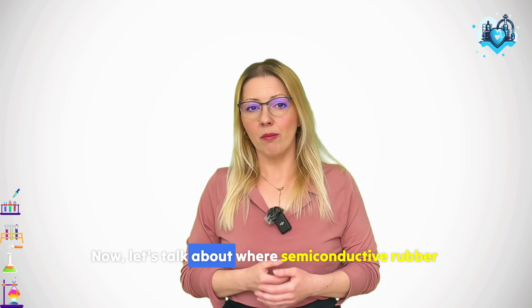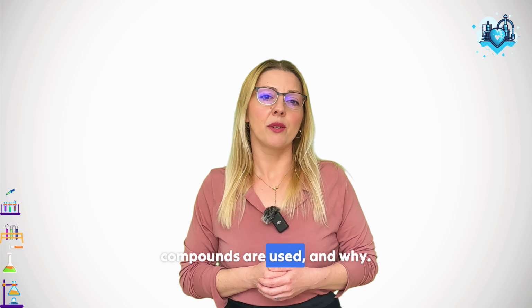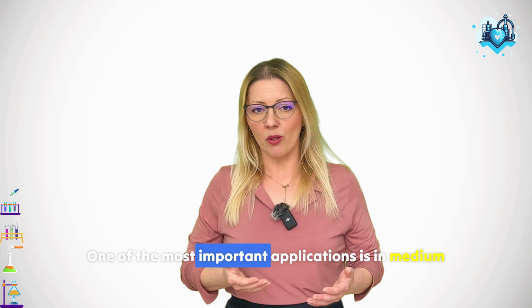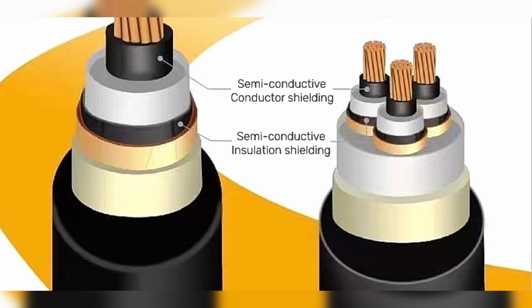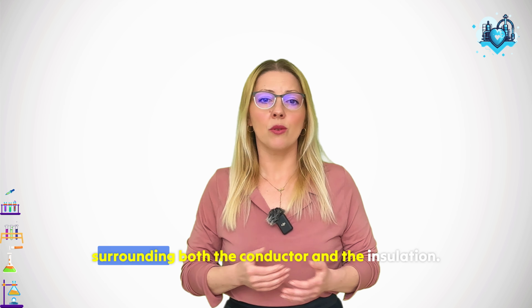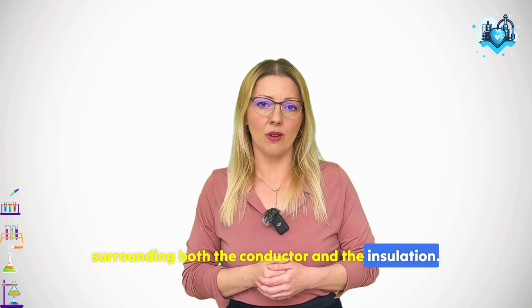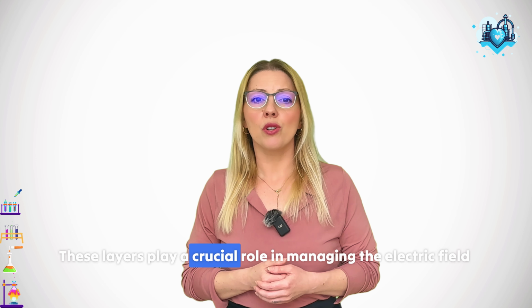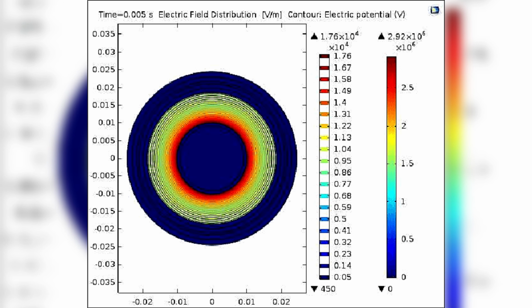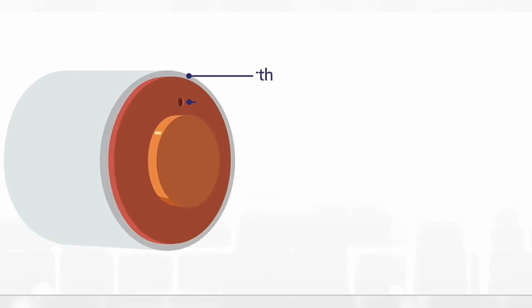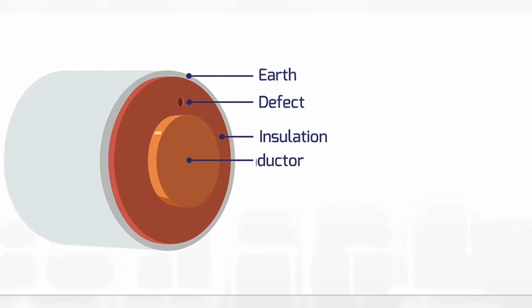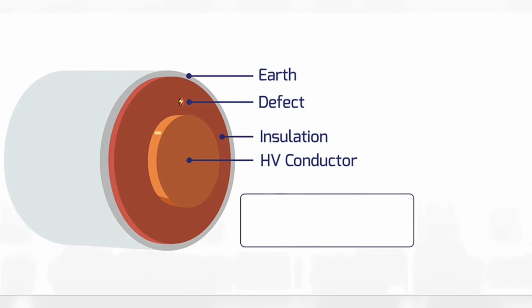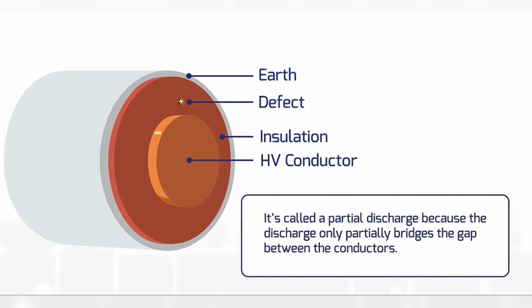Now, let's talk about where semiconductive rubber compounds are used and why. One of the most important applications is in medium and high voltage power cables, where you will find semiconductive rubber layers surrounding both the conductor and the insulation. These layers play a crucial role in managing the electric field within the cable. Without them, the sharp potential difference between the metallic conductor and the insulating rubber could cause electrical stress points, leading to partial discharges, insulation breakdown, and ultimately cable failure.